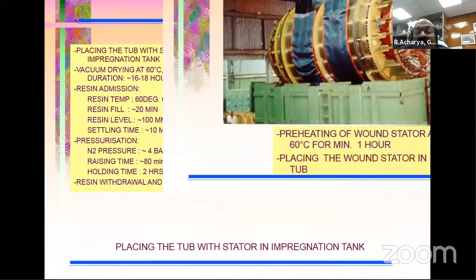First, it is placed inside a furnace where the temperature is raised to 60 degrees Celsius for at least 1 hour. After that, it is put inside a vacuum chamber and the hood is closed; a very high vacuum is created so that moisture and voids are sucked out. This high vacuum, of the order of around 0.2 millibar, is maintained for almost 16 to 18 hours, with qualitative checks to confirm adequate vacuum has been created and the winding is dry enough and ready for impregnation.